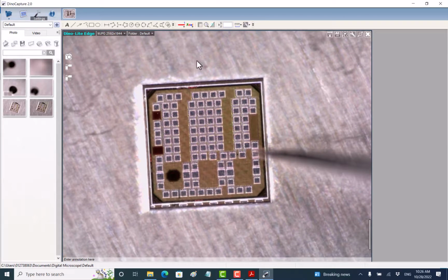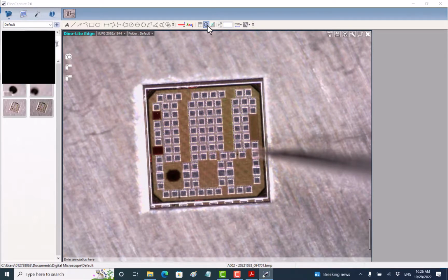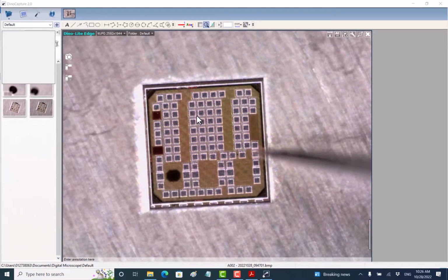Okay, and this software allows you to do some magnification. How do you do magnification? Which one? This one? Thank you. Got stuck. So if the software is not working, do not move the tip because it's not reflecting what's going on, and then you may crash.